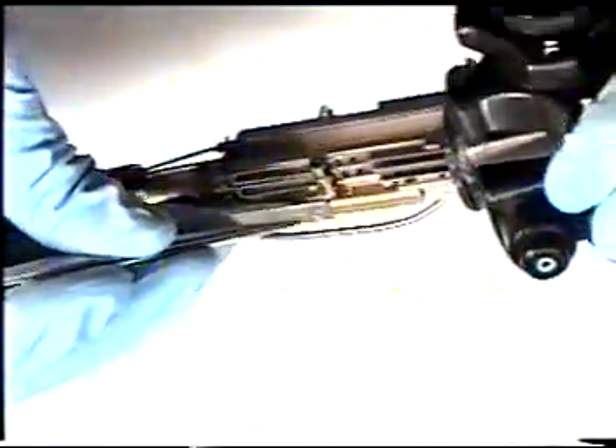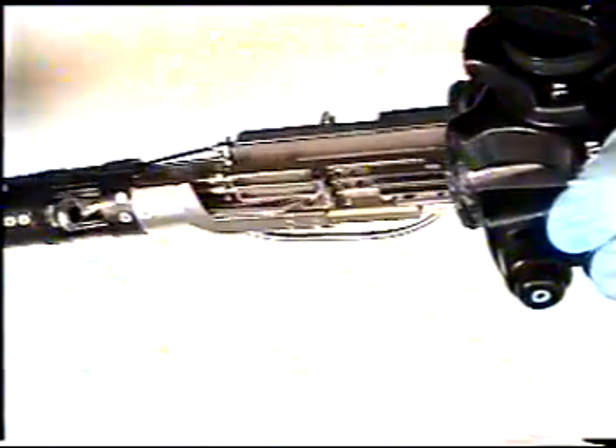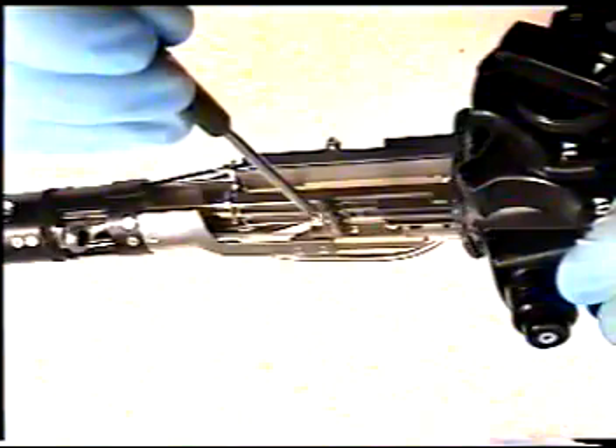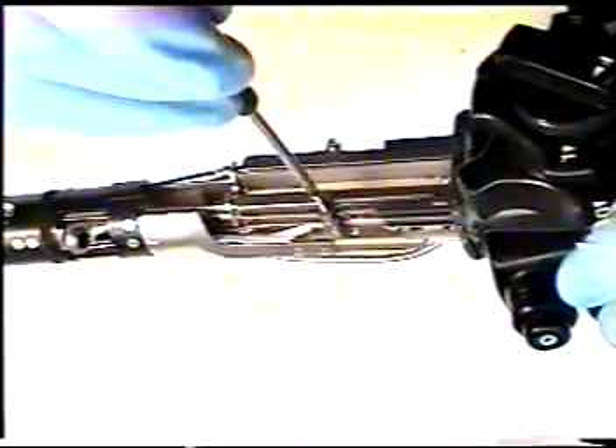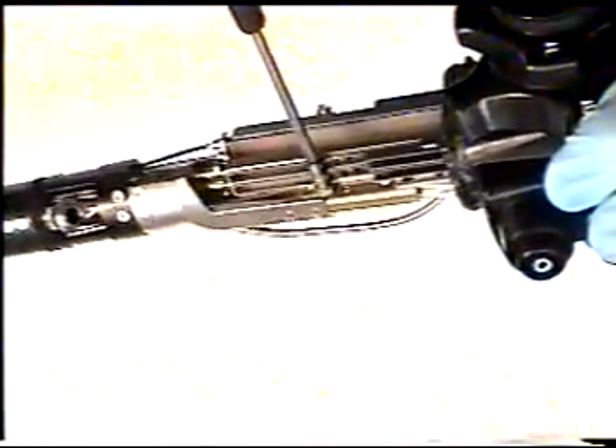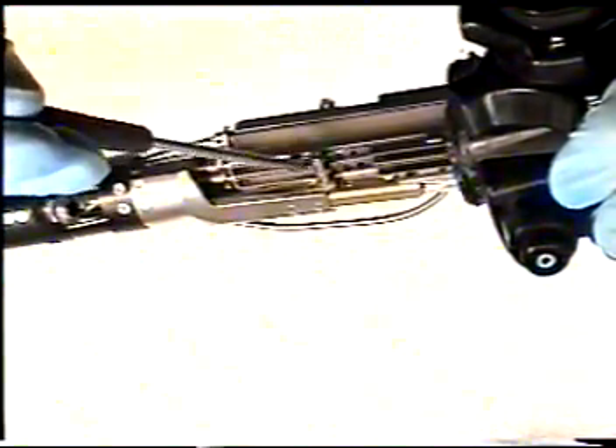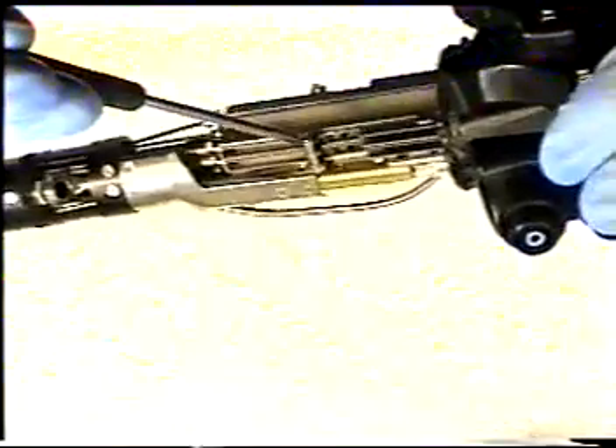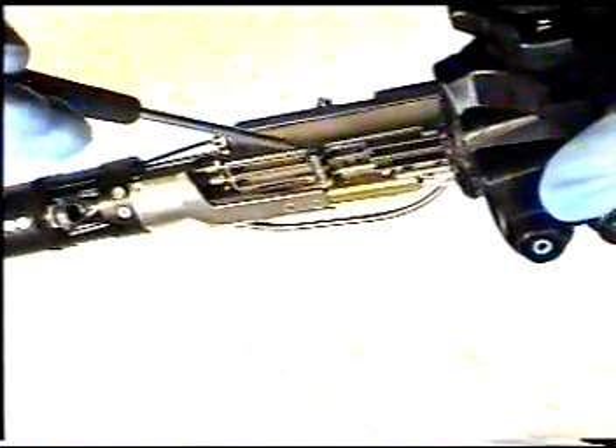Again, for the other two cables, once rails are straight and copper ferrules are in place, using Phillips and long stainless screw, slide screw down through rails and ferrules, again being sure that rails are in their proper slots and not overlapping in any fashion. This is a very dangerous situation, can cause the cables to lock up during procedure. Also, Loctite head of second screw.